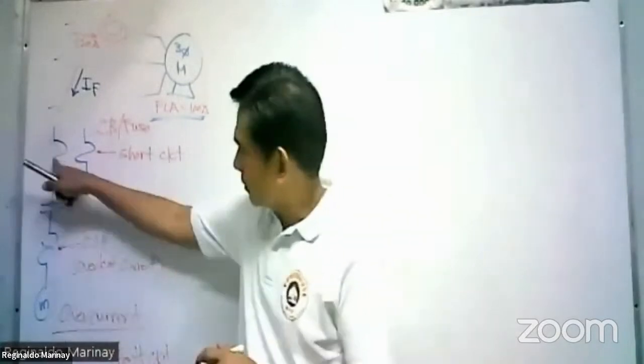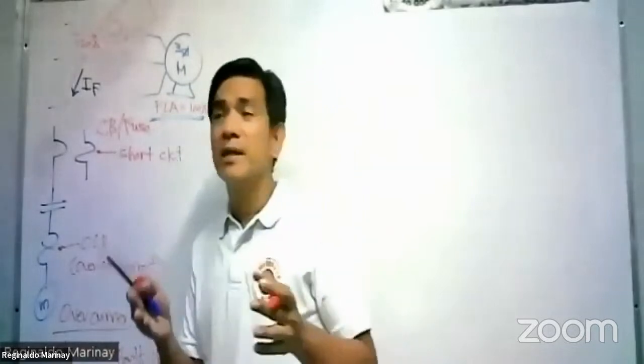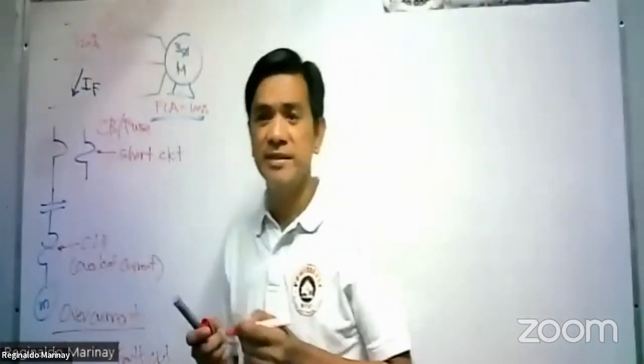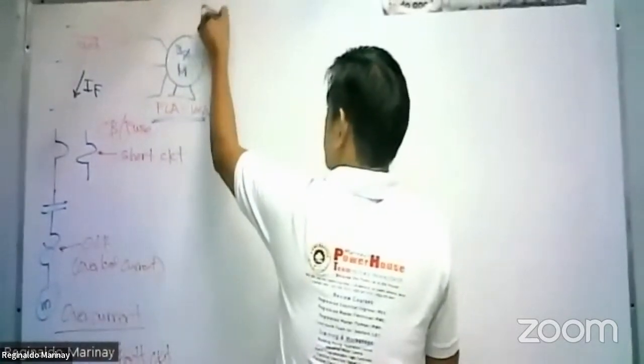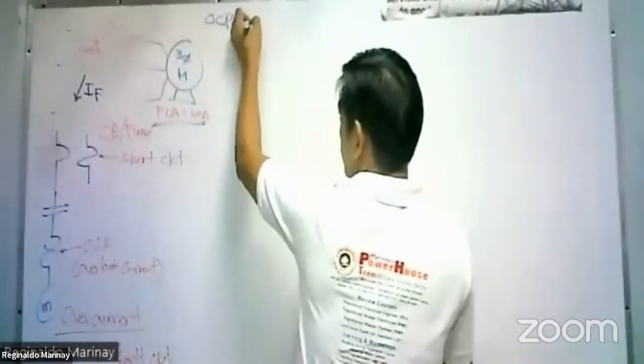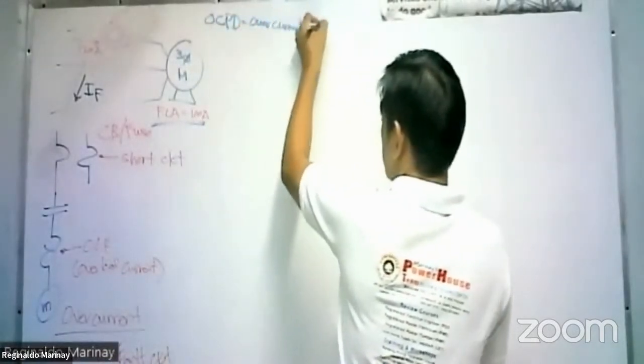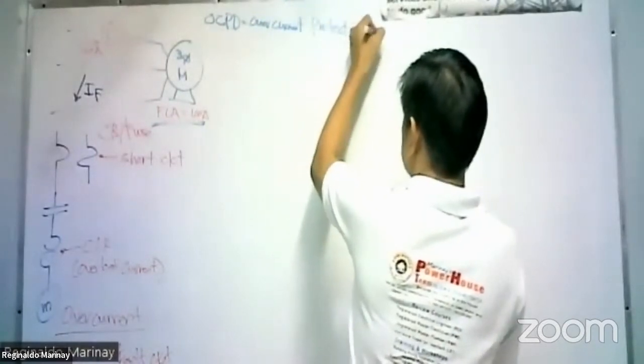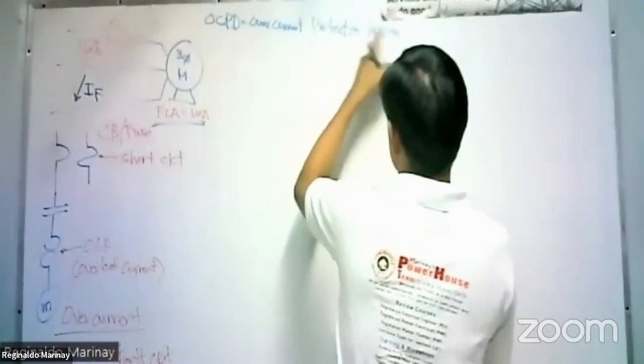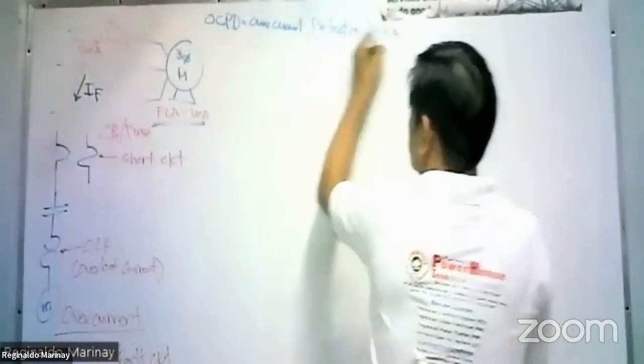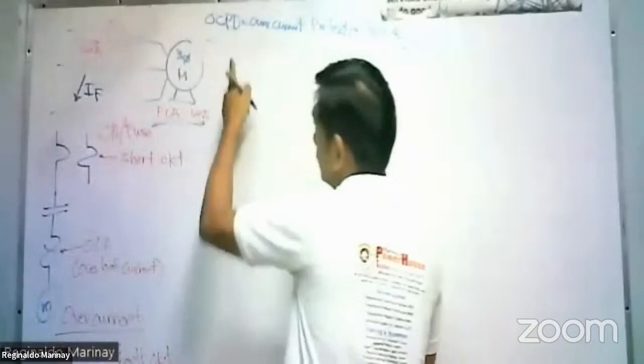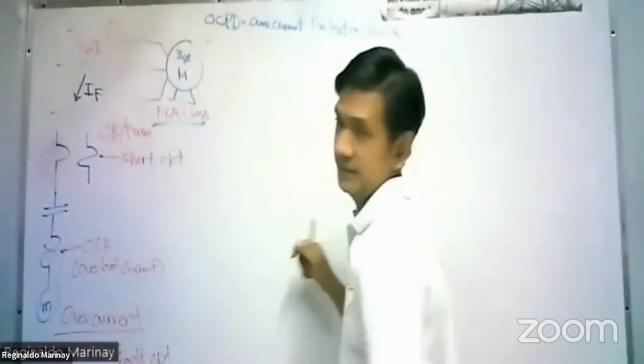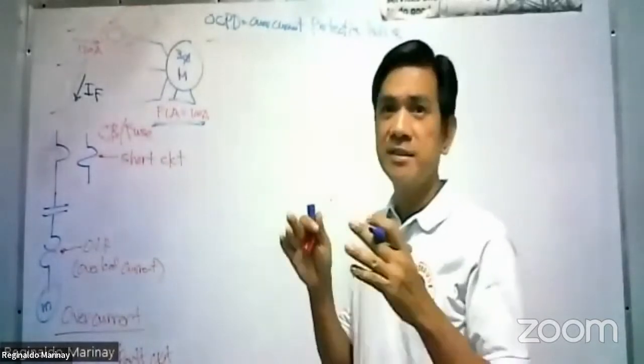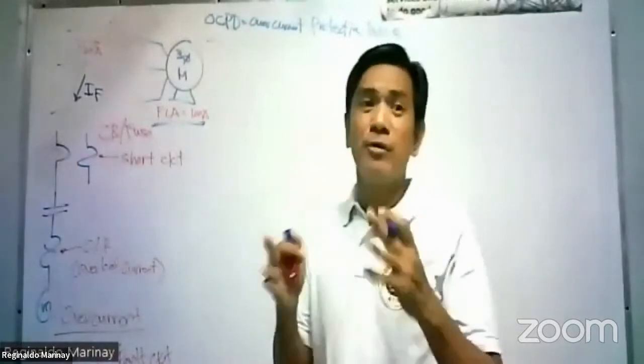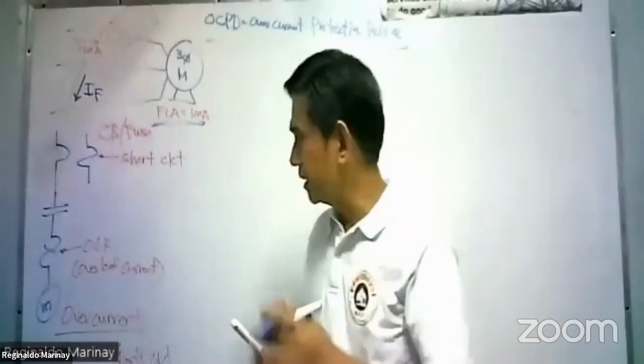That is why circuit breakers and fuses in the Philippine Electrical Code and also in the National Electrical Code of the US, they call this OCPD. What do we mean by OCPD? OCPD is what we call the overcurrent protective device. In our standard code, fuses and circuit breakers are called the OCPD, overcurrent protective device. Although nowadays there are some circuit breakers designed also for overload. The new technologies of circuit breaker.